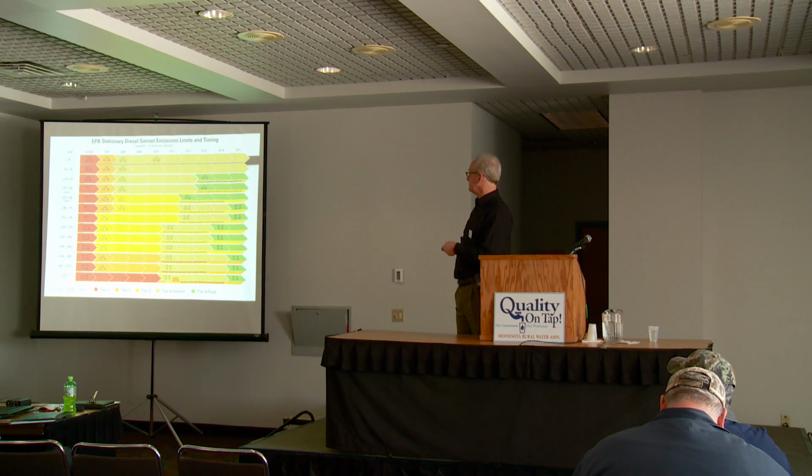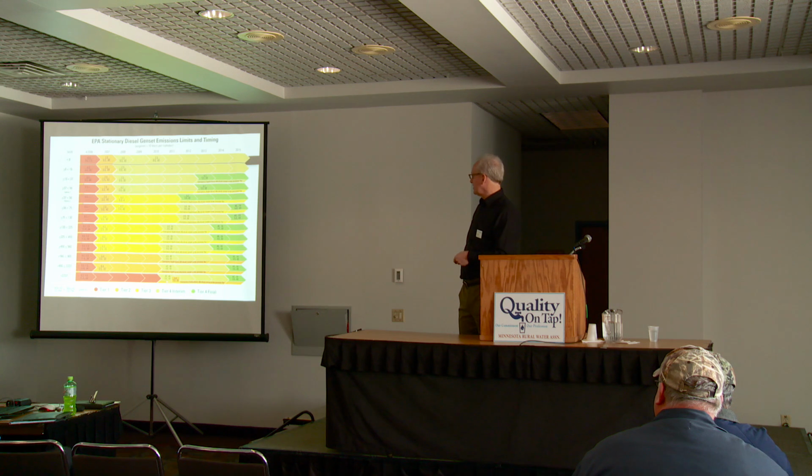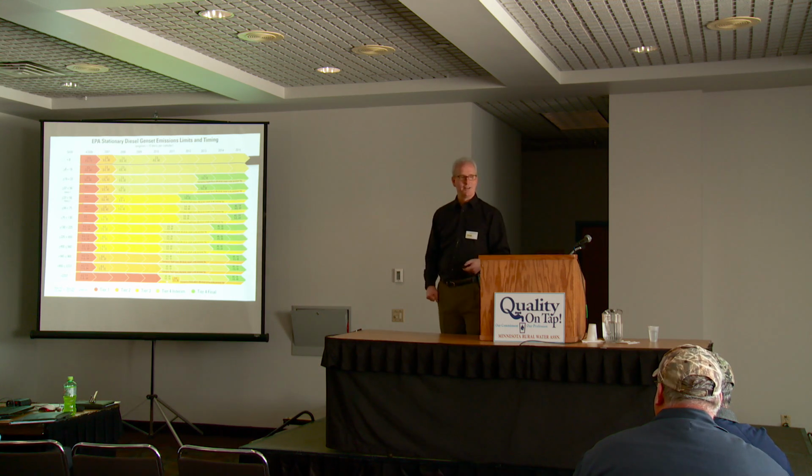Before 2011, you can see these were all solid colors. It's like it didn't matter what you did, you just bought the engine. But down here, in 2011, there's this little slide. I know you can't read it, but it says emergency application. It says after 2011, if you're doing non-emergency, you have to have this Tier 4 emission level. But if you're doing emergency only, you can use a Tier 2 emission level, this orange color. So now it gets more complicated starting in 2011.